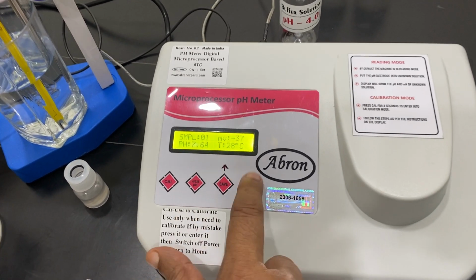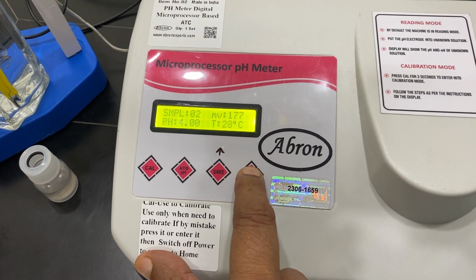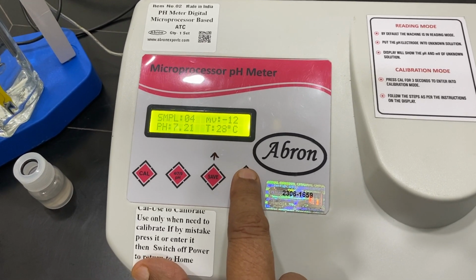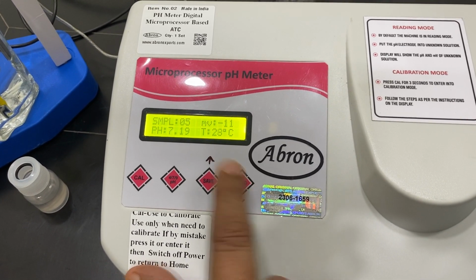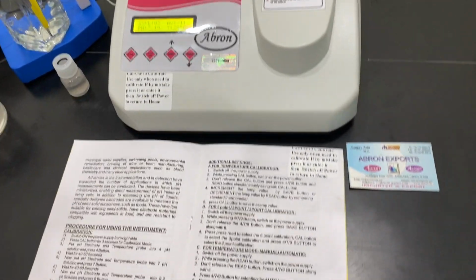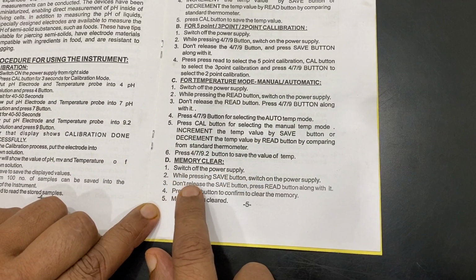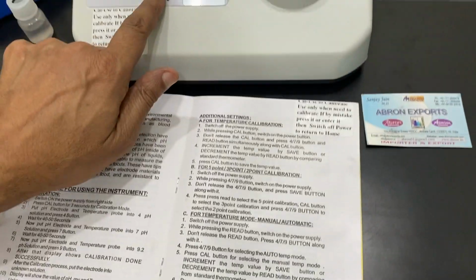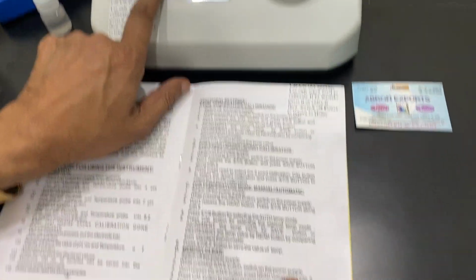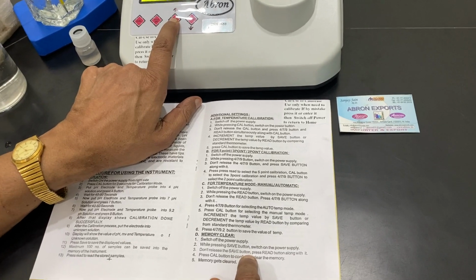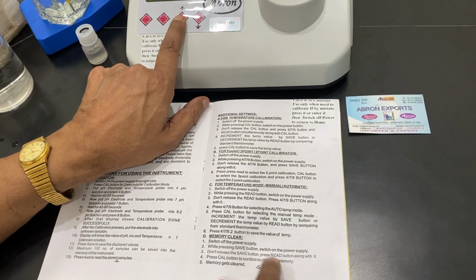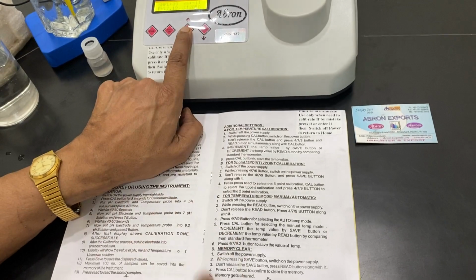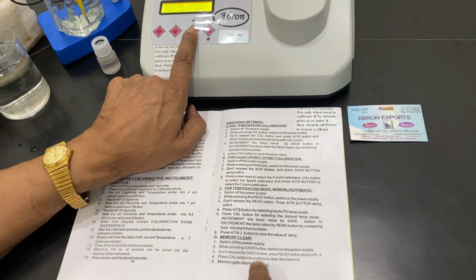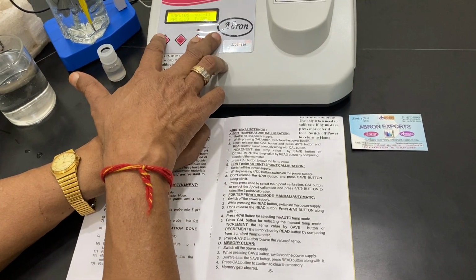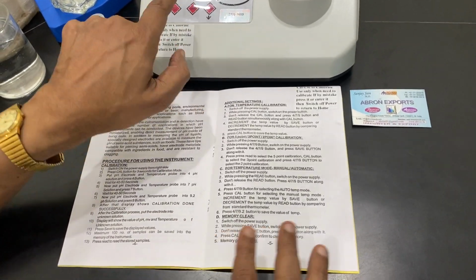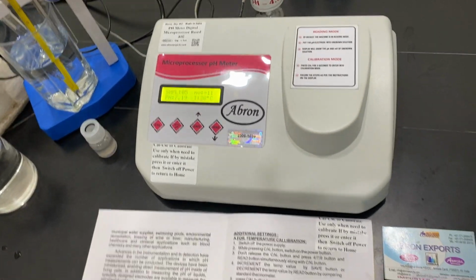It will show the 1st sample, 2nd sample, 3rd sample, 4th, 5th, and up to 100 samples can be stored. If you want to clear this, switch off the power supply, press the SAVE button, and switch on the power supply. Don't release the save button, and press the read button along with it. Then press the calibration button to confirm the clear. Then it will clear the memory. Better avoid it unless it is very much required.